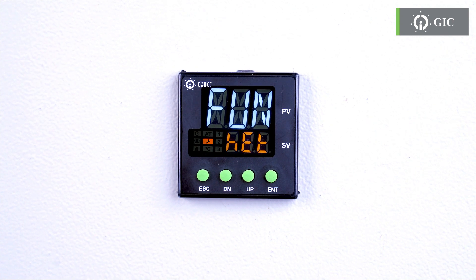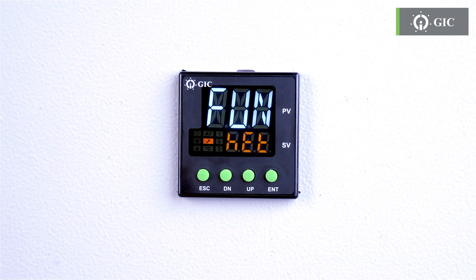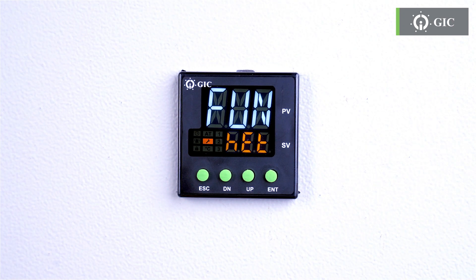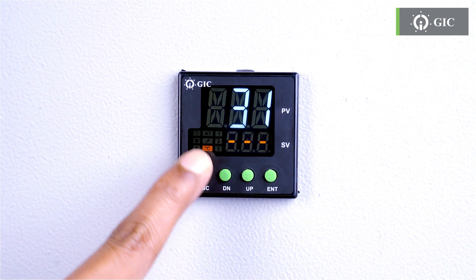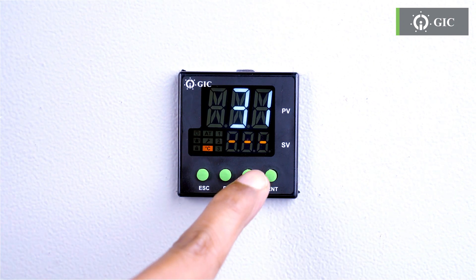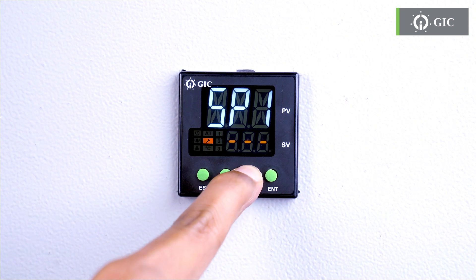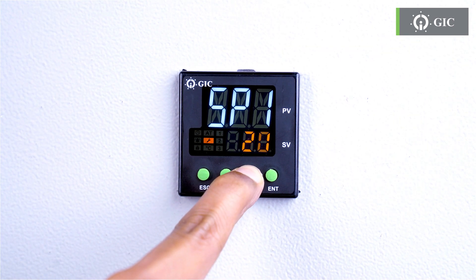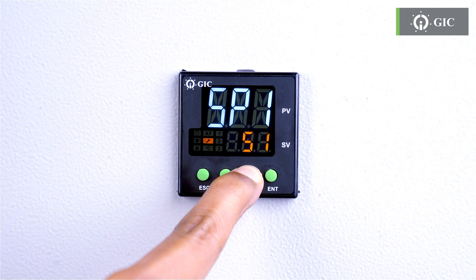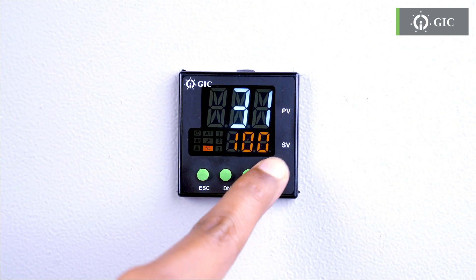Now you'll see FUN on the display, which means function. We're using the heating function for this example, so no need to change the menu. Just press ESC to return to the main screen. To set the set point, which is written as SP, press the up key once to reach the SP1 menu. Then press the up or down key to set the desired temperature. Finally, press enter to save.